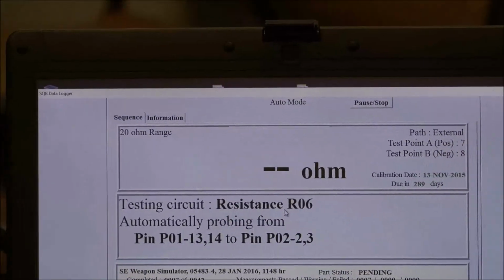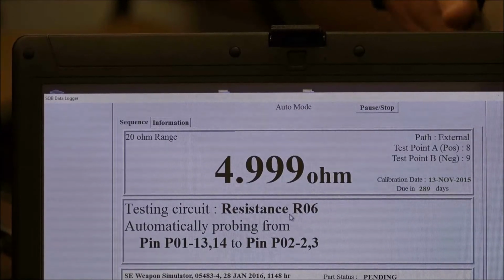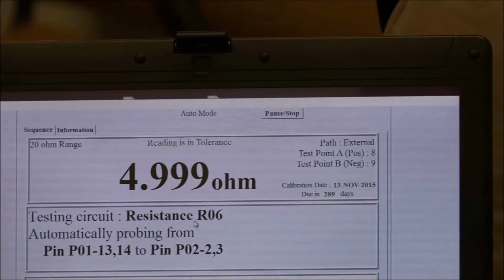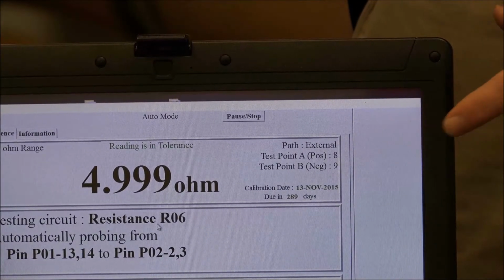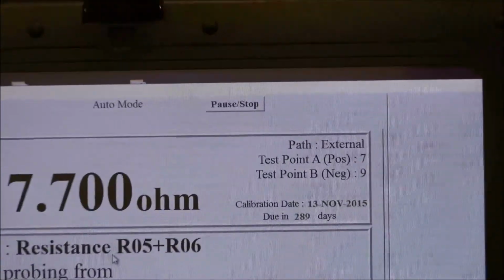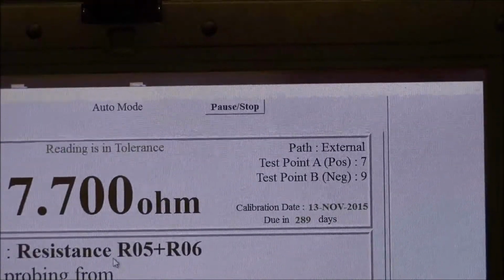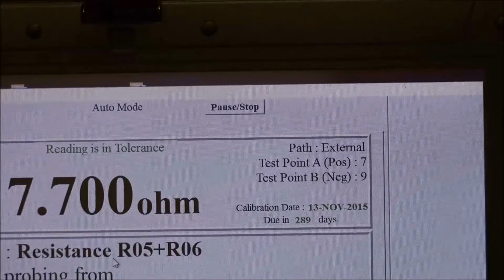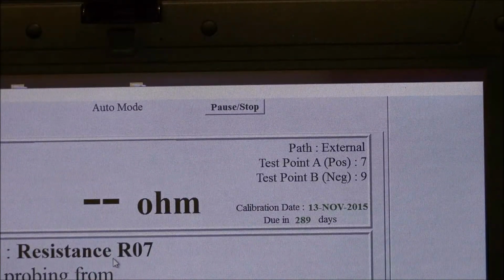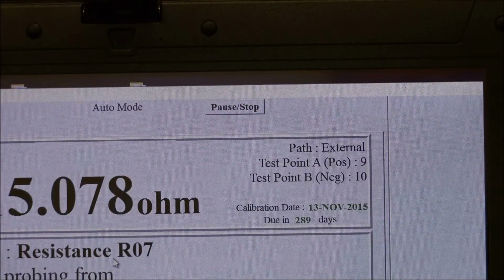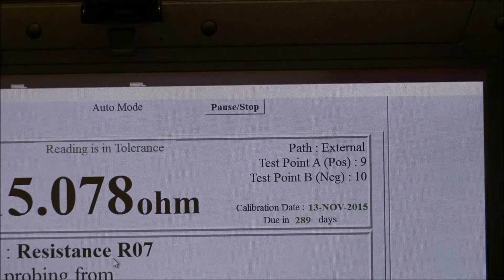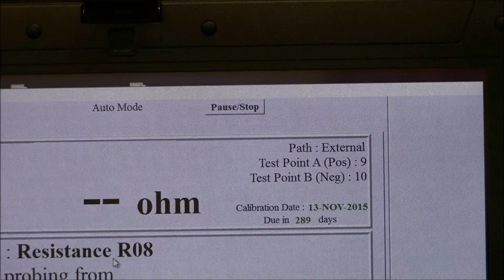We also show the calibration date and how many days out of cal you are. This is taking the calibration information from the tester. This will show green if you're comfortably within cal. If you're within 30 days, it will turn yellow, warning you that you're about to go out of cal. And when you do go out of cal, it turns red and will not allow you to run measurements. The unit will not accept data that isn't with a cal meter.